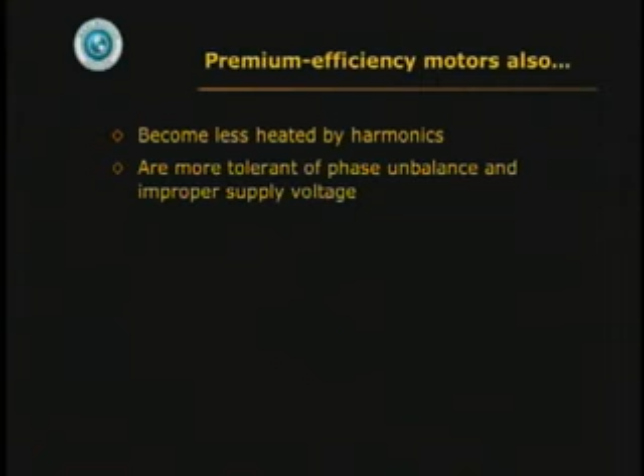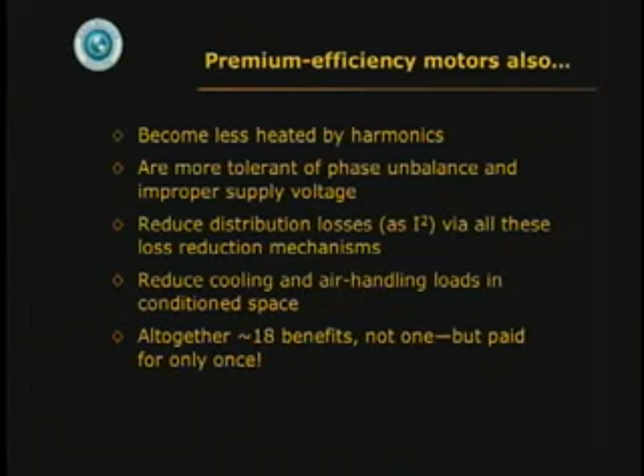Also, the premium efficiency motors are less heated by harmonics. They're more tolerant of unbalanced voltage in the phases, improper supply voltage. They reduce distribution losses and cooling and air handling loads. 18 benefits, not just one. But you pay for it once. So if you add all that up, you're going to get bigger savings.